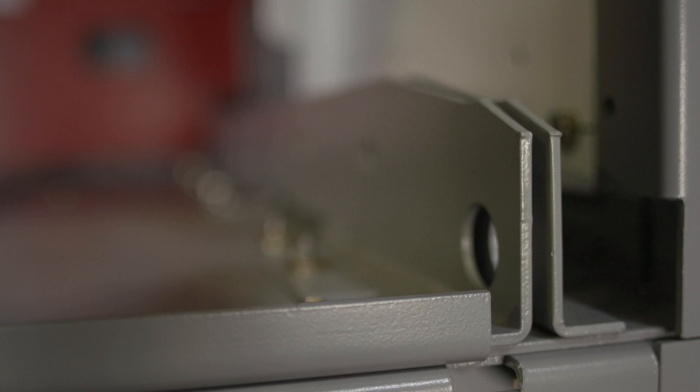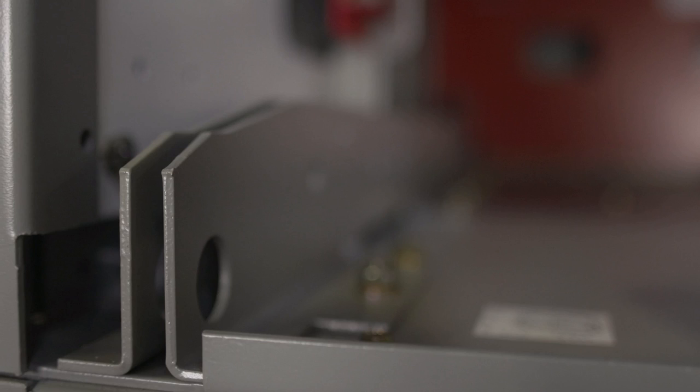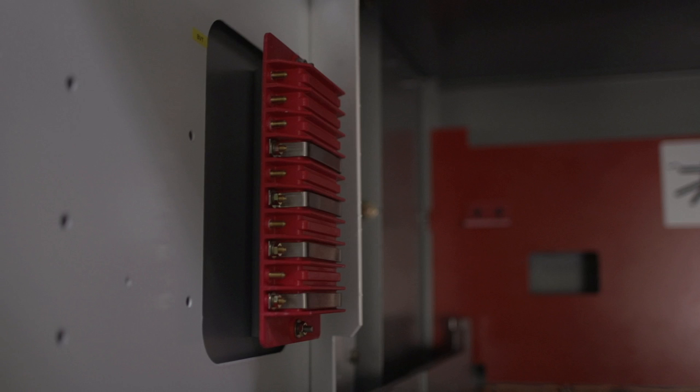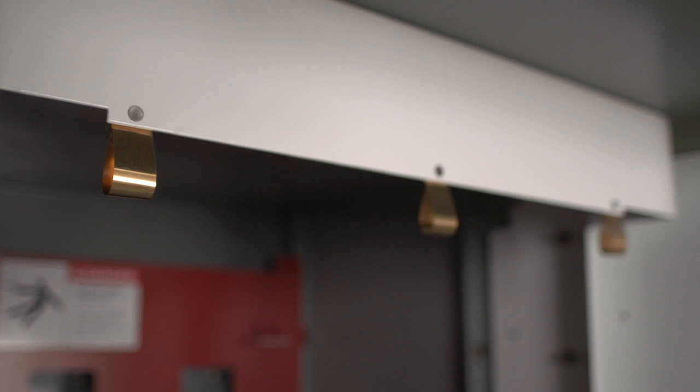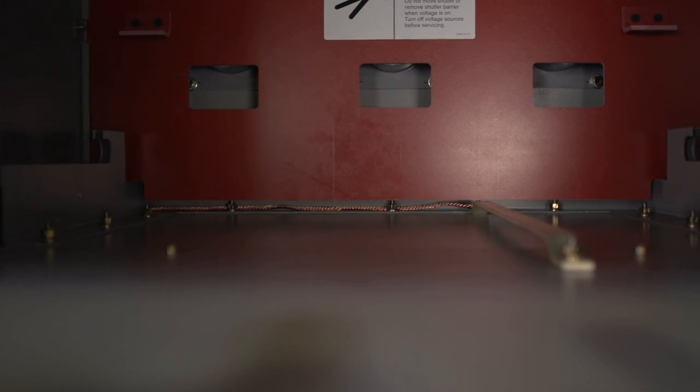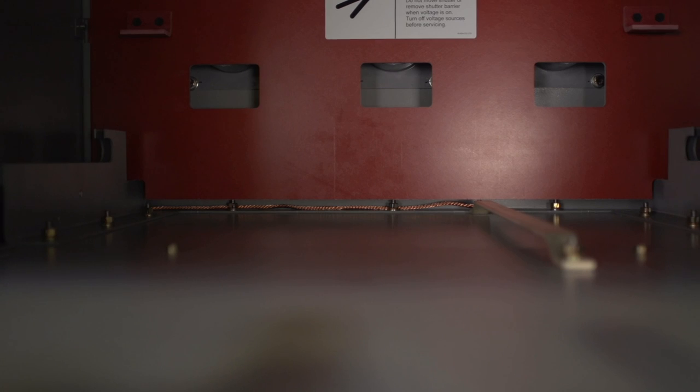This is the auxiliary voltage transformer compartment. If the compartment is utilized, the extension rails are the exact same as those on the lower compartments and are also the exact same for trays and circuit breakers. Extension rails are used to facilitate the insertion of the tray into the compartment and allow for complete withdrawal from the cell. On the left we have the secondary disconnect terminals for secondary wiring. As the tray slides in, these connect. On the top we see the ground contact system, which removes static charges from the instrument transformer or fuse. Underneath the tray we have the grounding system.